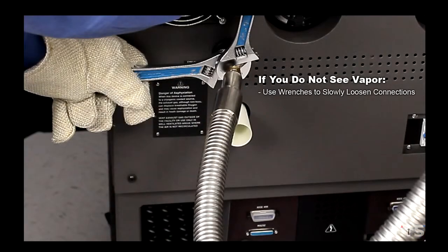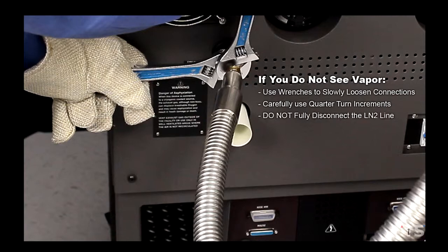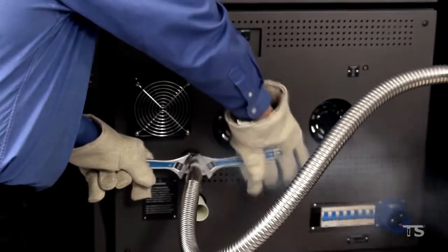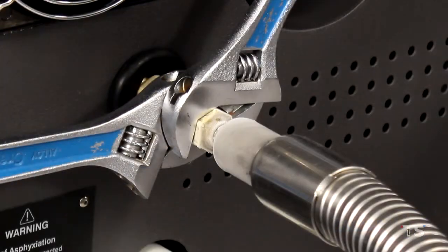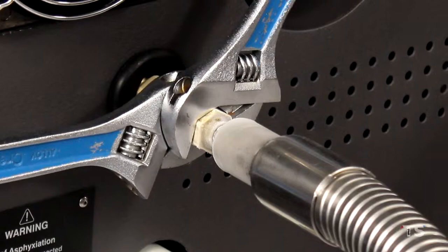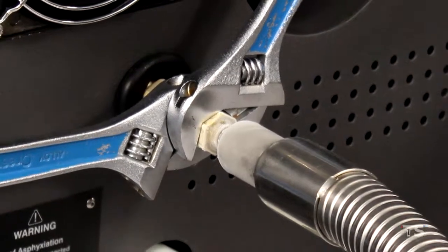If you do not see the vapor, use your wrenches to slowly loosen the hand-tightened connections. Carefully use quarter-turn increments. You do not want to fully disconnect the LN2 line from the cryo inlet. Once you are sure that gaseous nitrogen vapor is present, wait for the cryo inlet fittings to frost up. Once the fittings have frosted up, use your wrenches to fully tighten the connections.